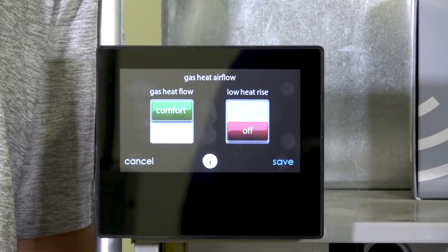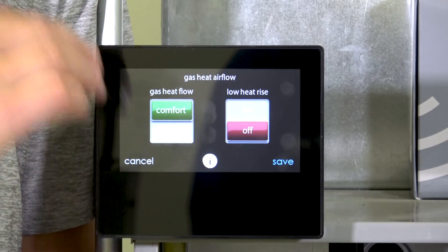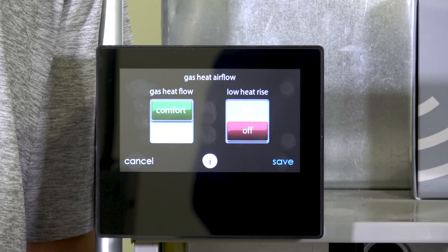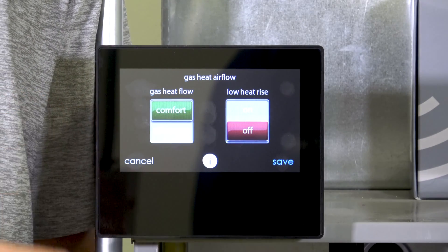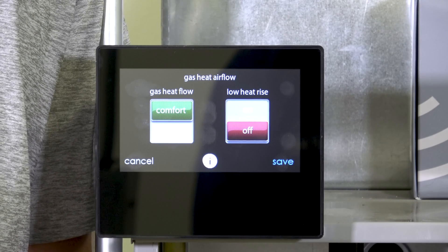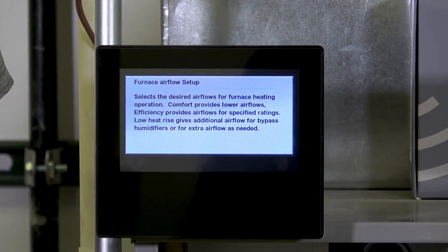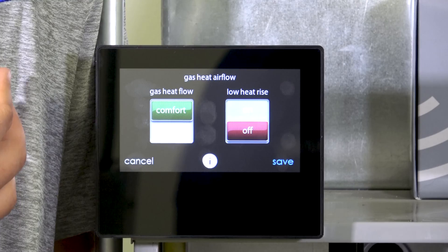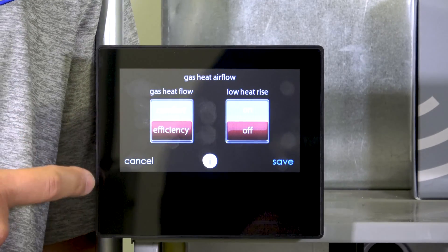Gas heat airflow — I'll admit I do not like this screen. It's very frustrating. If I don't have enough airflow on my project to get air to the furthest duct runs, I can tell the furnace to run at higher airflow in heating mode. I can choose Comfort or Efficiency. I'd personally prefer it say Low or High, but it says Comfort and Efficiency — I forget what it means every time. Pressing the Info button shows that Comfort provides lower airflow, but since green means more to me, it's counterintuitive — it's actually the opposite.